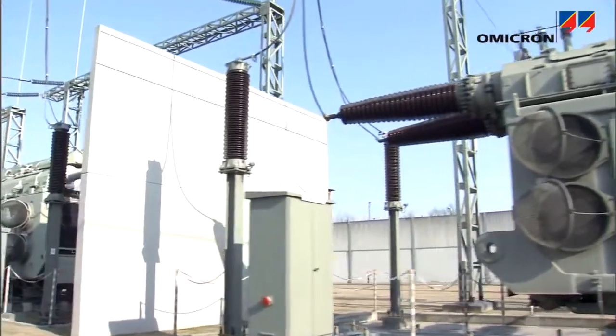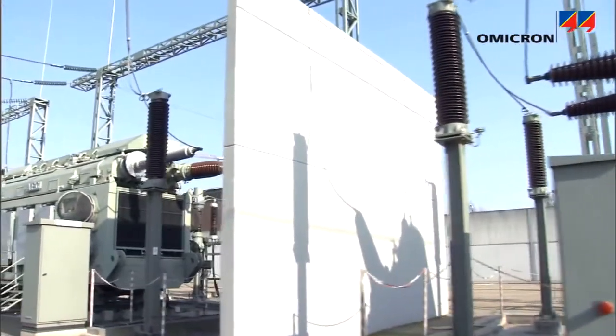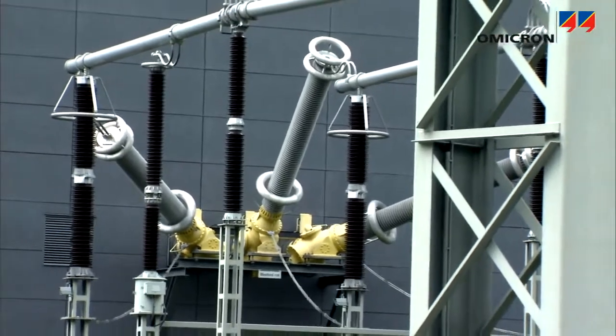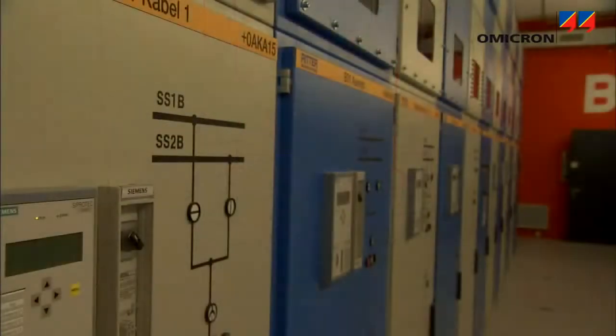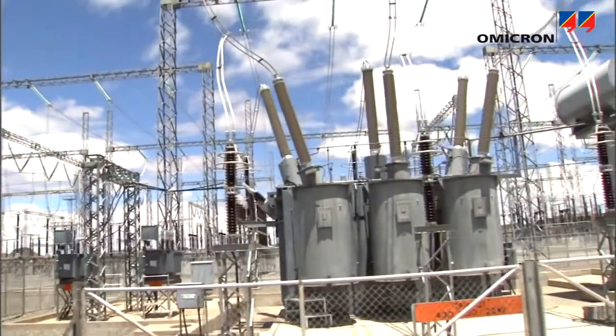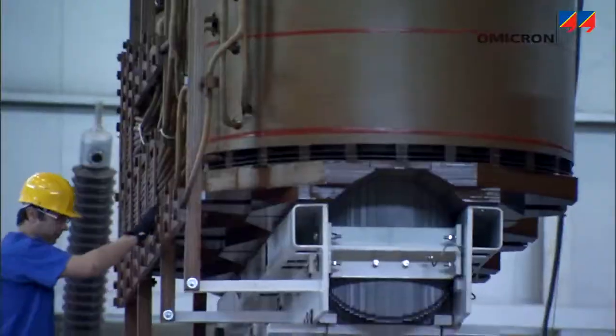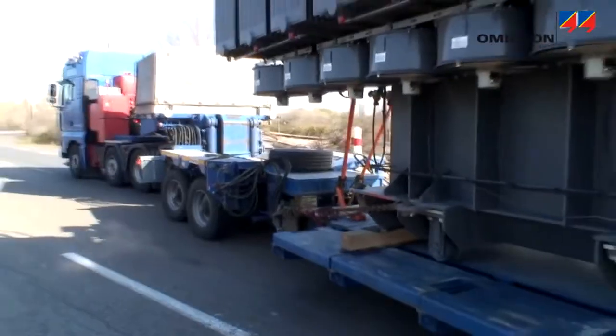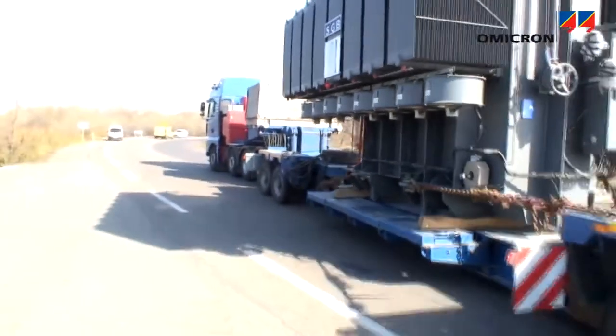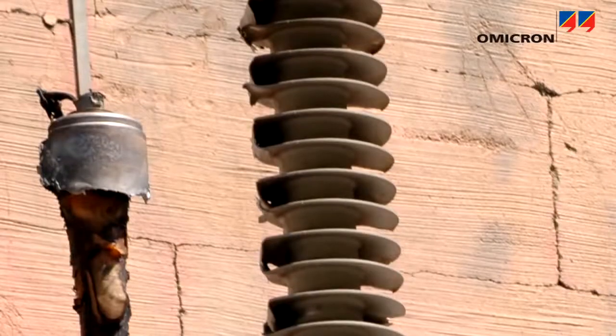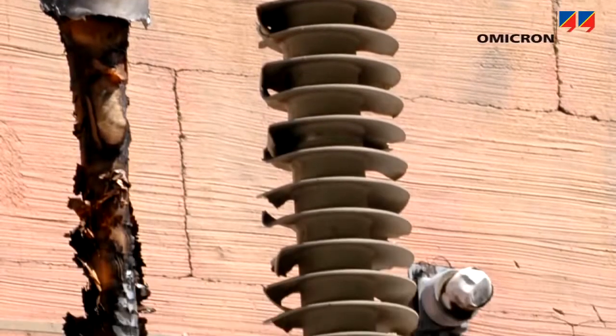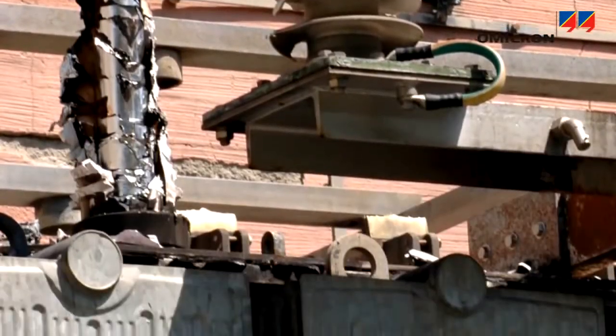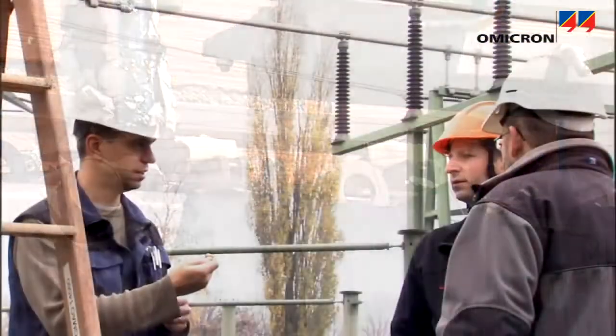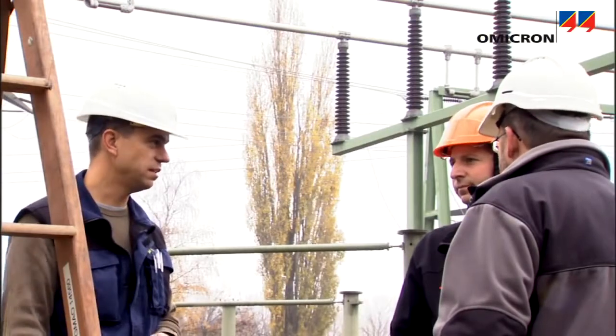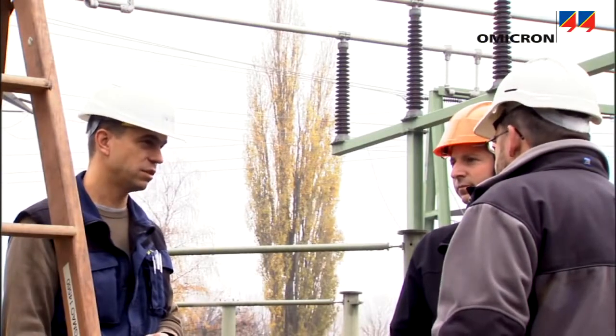Power transformers transform electrical energy from one voltage level to another by stepping voltages up for transmission to minimize losses, or down for distribution. They belong to the most valuable assets of a utility. Manufacturing a new transformer and transporting it to site results in substantial costs. However, the damage caused by a transformer failure and the subsequent loss of production may end up costing far more. Utilities therefore try to keep their transformers in operation for as long as possible.